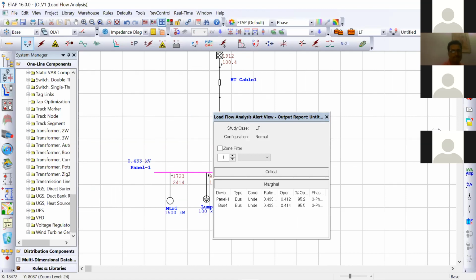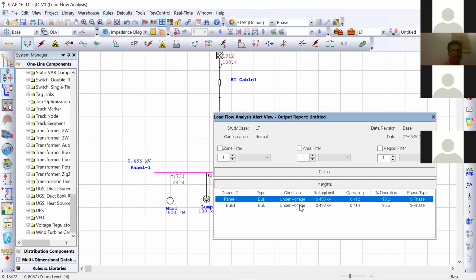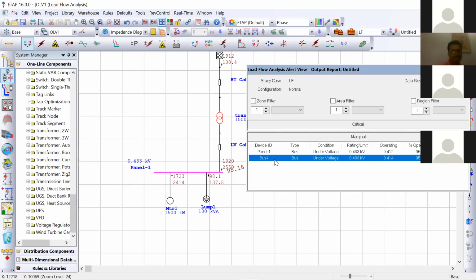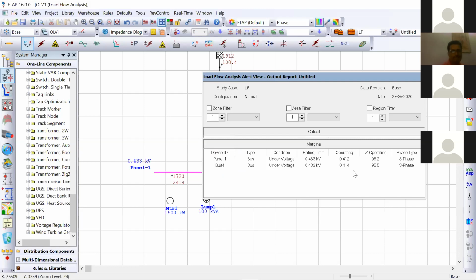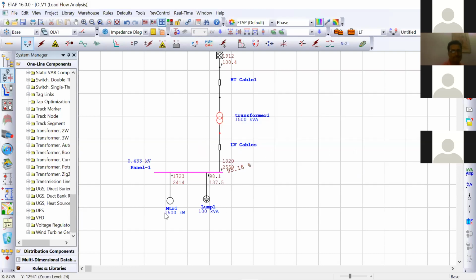The system will give you alarms that these 2 buses are facing under voltage. Panel number 1, that means this bus is now facing under voltage and this bus is also facing under voltage. That means the transformer itself is facing under voltage. So these types of things you can always cross check prior to design, prior to deciding the rating of the components. This 1500 kilowatt motor is quite large for this 1500 kVA transformer. So either I have to reduce the rating of the motor or increase the rating of the transformer. Sectional losses also I can check with this.